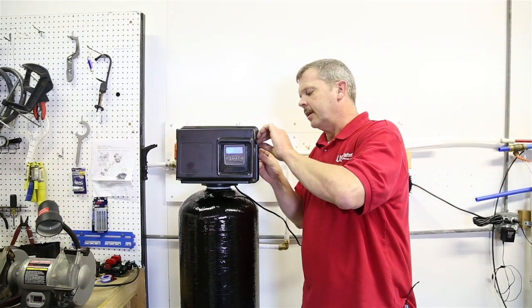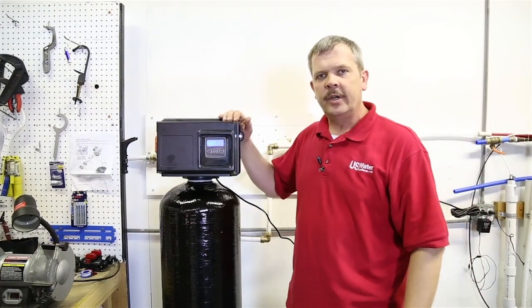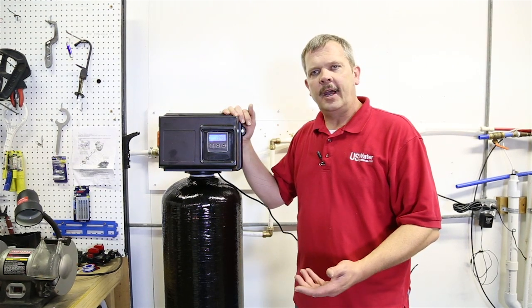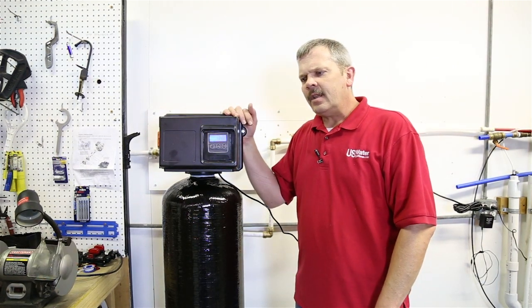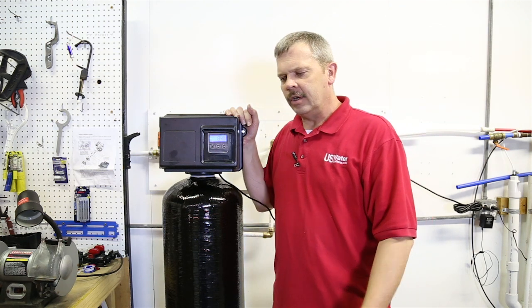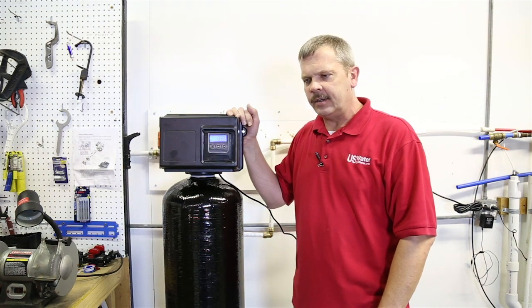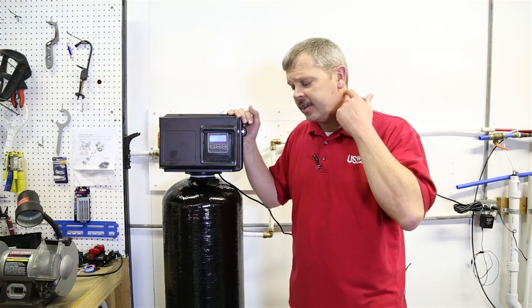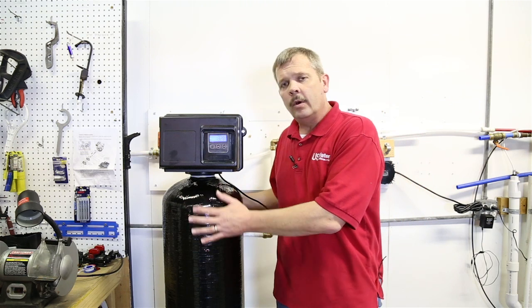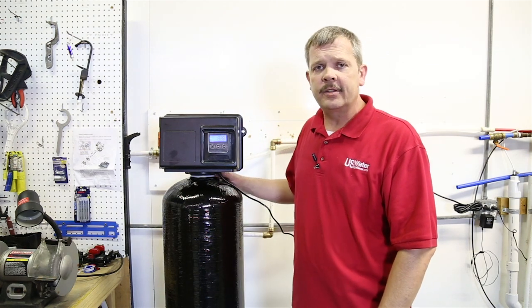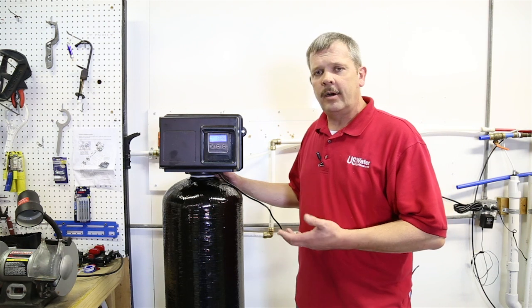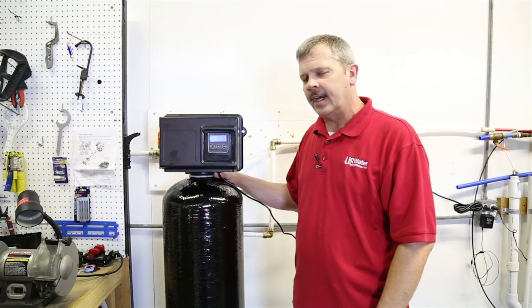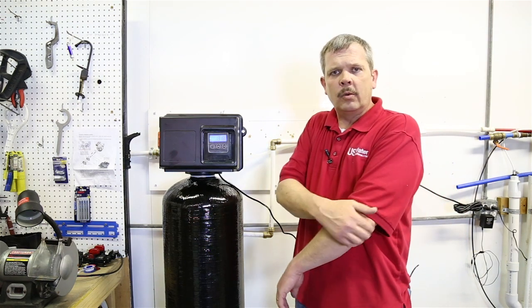Now, going forward, this is going to backwash based on how many days you put in between the actual regeneration process. From there, it should work fine. Now, if you see that you're doing fine after a day and you want to extend to two days, you can do that. But if you start to see any kind of trace of iron start to show through, then go back to one day because you don't want to load this thing up with iron because if you do, it's really difficult to get it cleaned out. So it's important that we regenerate often enough that we never deplete this air pocket.